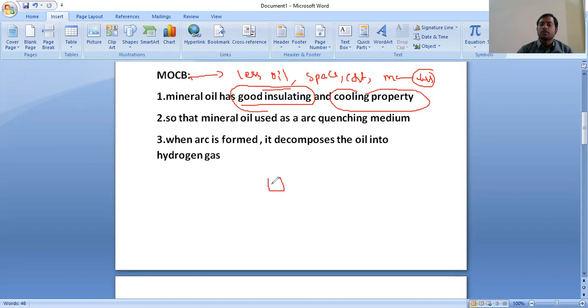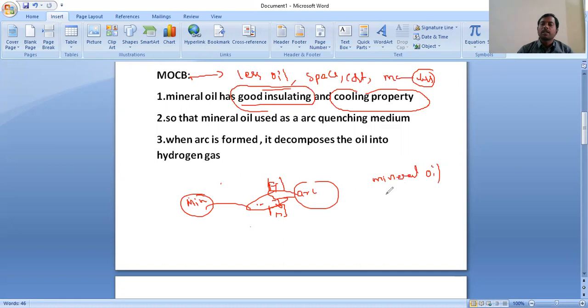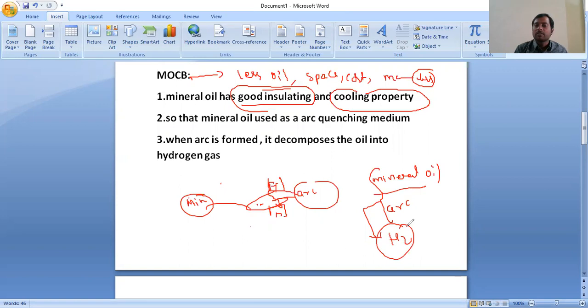For example, this is the fixed contact and another one is the moving contact. Between these two contacts, arc will be formed. This arc will be neutralized by the mineral oil. Whenever the mineral oil reacts with the arc, then because of this reaction, hydrogen gas will be formed. This hydrogen gas has good cooling properties. As we know, arc is nothing but heat — more heat. So immediately we should reduce that heat, that's why mineral oil is used.